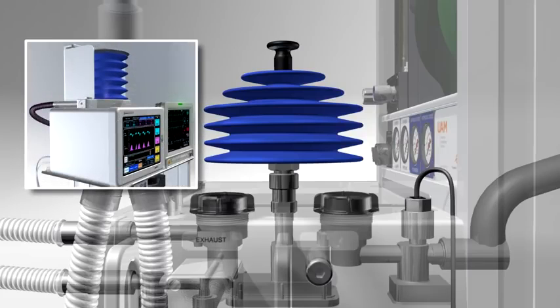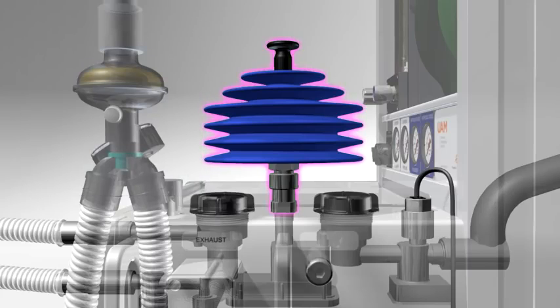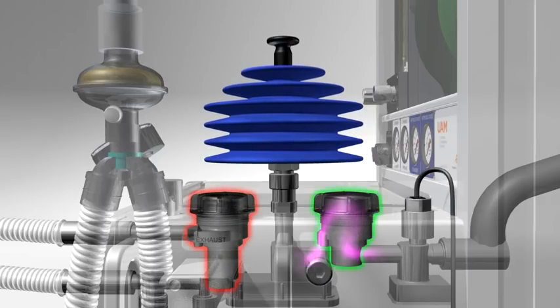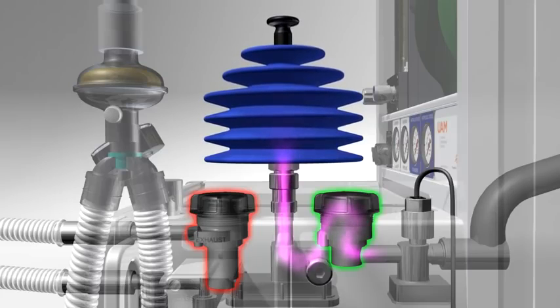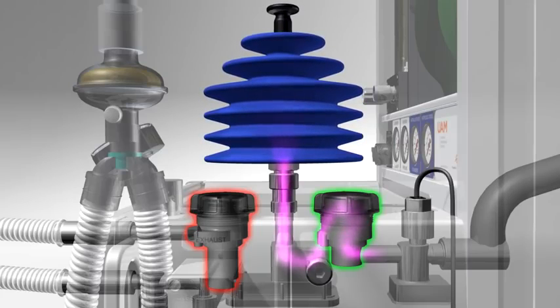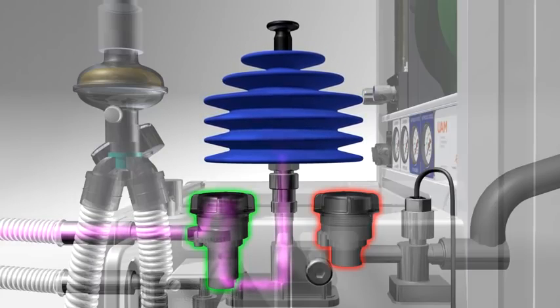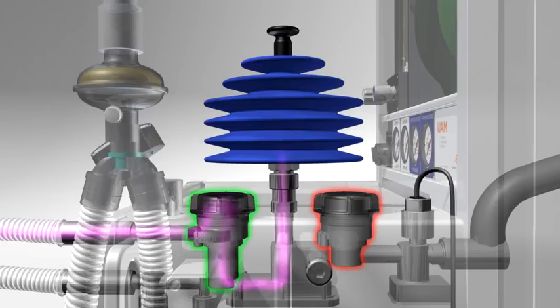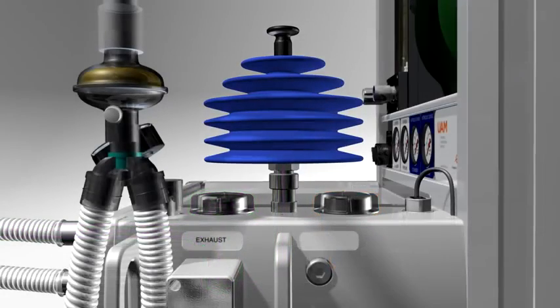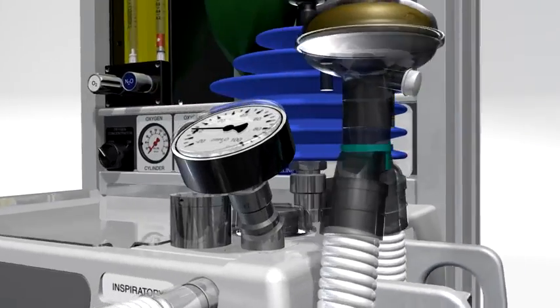The UAM supports both automatic and manual intermittent positive pressure ventilation or IPPV. The bellows between the one-way valves are used for manual IPPV. When the bellows are raised, gas flows through the first non-return valve into the bellows. The second non-return valve remains closed. As the bellows are pushed down, the gas flows out through the second non-return valve into the inspiratory limb. The first non-return valve is closed. Another pressure relief valve ensures that excessive manual force on the bellows cannot cause harm to the patient.